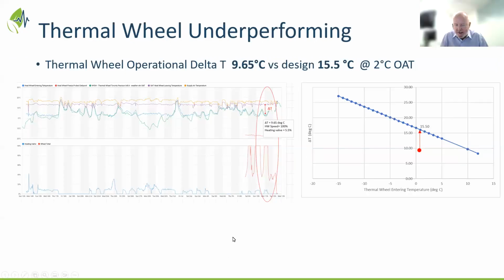Okay, and we're speculating at this point on what gets in the way, or whether it's air imbalances between supply and exhaust, because air testing hadn't been done. Did any of them have air test reports on either side of the wheel? No, if there were, they were probably old reports. Some of the facilities had airflow monitoring stations, so we used those to determine it, but most of the facilities didn't have testing reports. Either they were there, but too old to rely on. Okay, thank you. That's helpful.